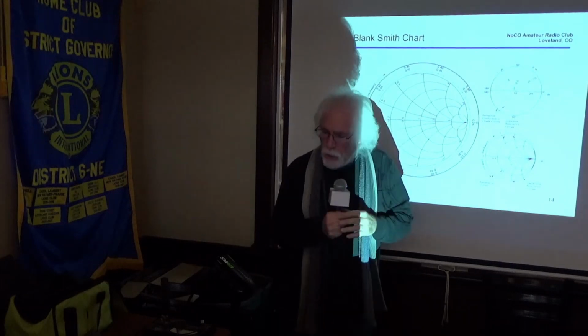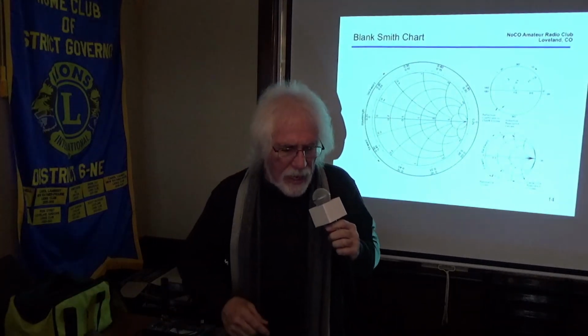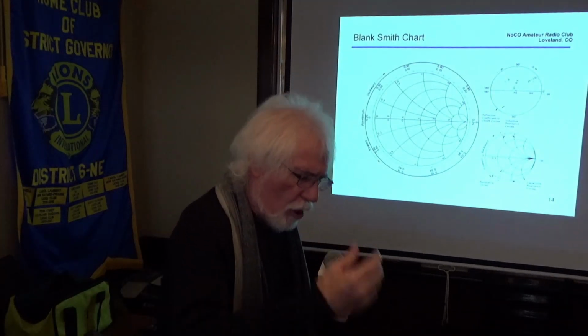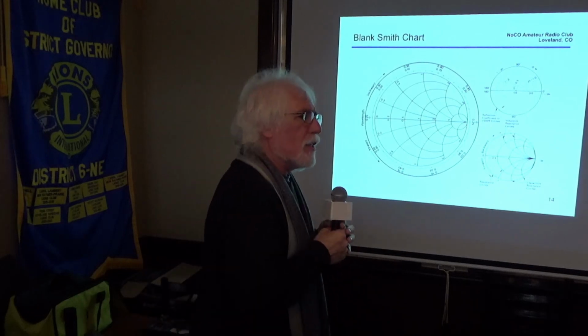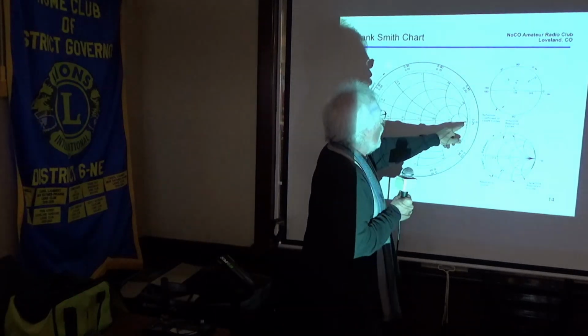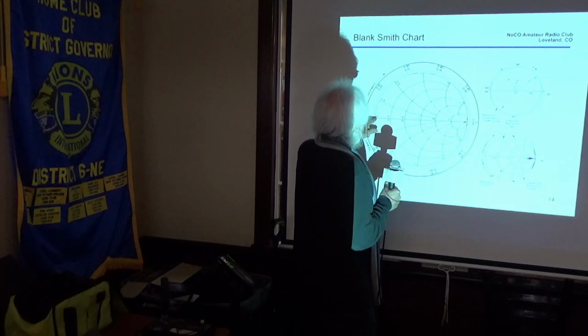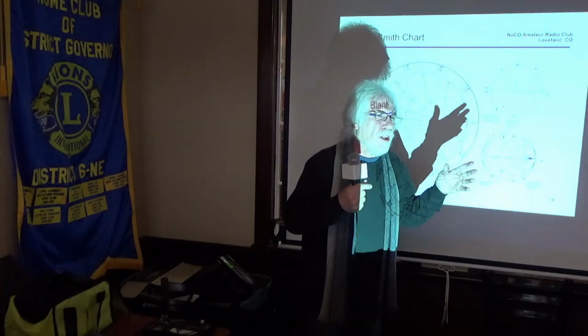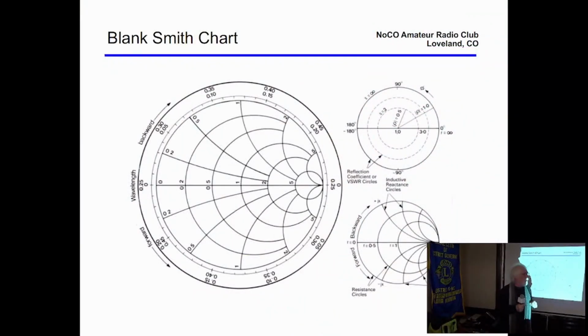So when we use these standards and calibrate our device, we adjust things so that our open circuit appears here. When I say we adjust it, we don't adjust anything. The computer inside here, a little microprocessor, figures out the particulars. We tell it, this is an open circuit. And it's like, okay boss, there's no short circuit. Got it. And then it goes and does its calibration over the range of frequencies that we want.